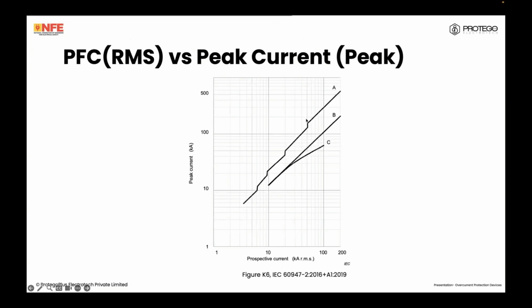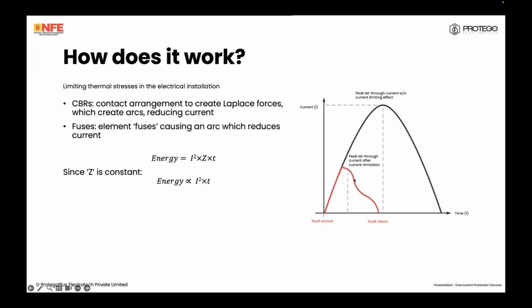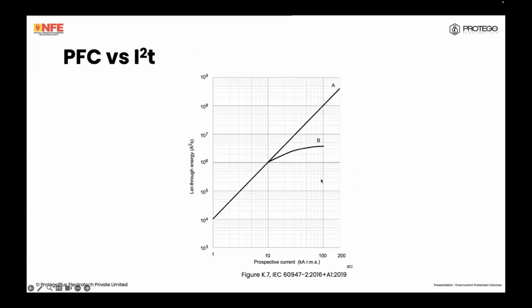Just ignore this A curve for now. This is something called asymmetric peak current. Generally, we look at symmetric peak current over a long amount of time. So see, without the breaker, there's a prospective current and a peak current. This has a ratio, I believe, of 1.414, which is root 2. With the circuit breaker or the fuse, this value is reduced, so we are able to essentially limit the peak current. This is obviously also provided as a prospective current RMS to let through energy for our cable calculations. Just keep that in mind. Again, without the overcurrent protection device and with the overcurrent protective device, you can see it sort of plateauing here.